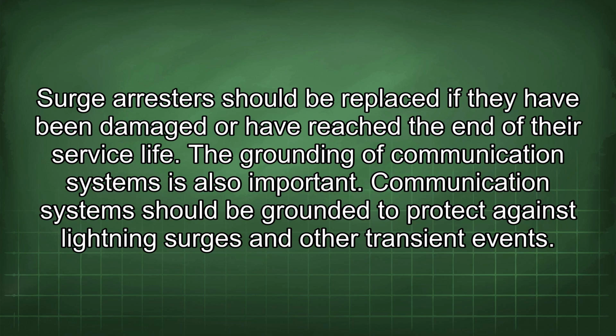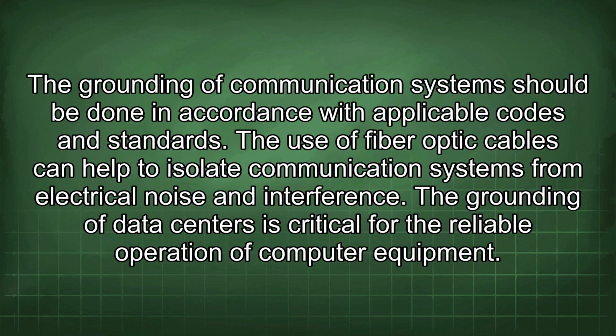The grounding of communication systems is also important. Communication systems should be grounded to protect against lightning surges and other transient events. The grounding of communication systems should be done in accordance with applicable codes and standards. The use of fiber optic cables can help to isolate communication systems from electrical noise and interference.